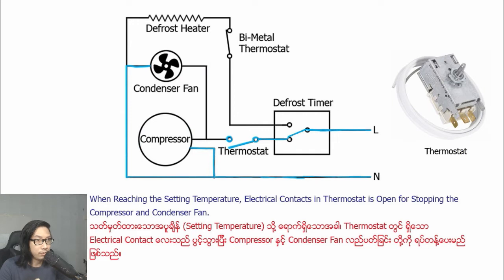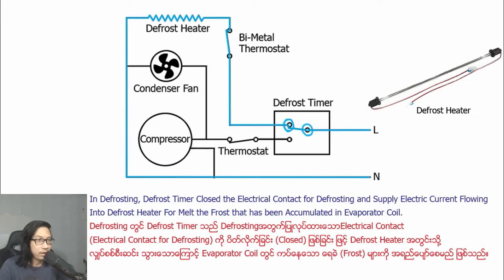When the set temperature is reached, the electrical contact in the thermostat opens, stopping the compressor and condenser fan. In defrosting mode, the defrost timer closes the electrical contact for defrosting and supplies electric current to the defrost heaters to melt frost.